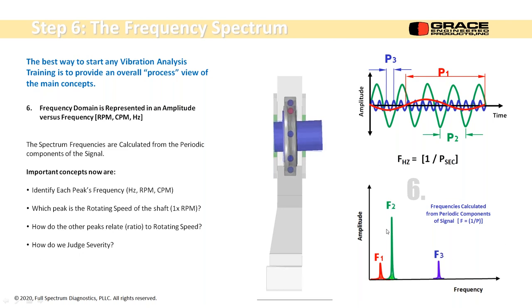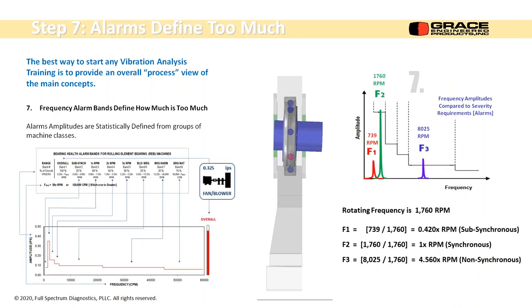The last concept is, how do we judge the severity? We don't have any criteria quite yet. That's on the next slide. Now, this looks complicated, and it's pretty easy. Once you have it set up, it's kind of a cookie cutter type thing. So this was setting up alarm bands for bearing health, for rolling element bearings. We're going to use this parameter. We'll have an overall level, which comes from whatever machine we have. So our overall level is going to be 0.325 inches per second.